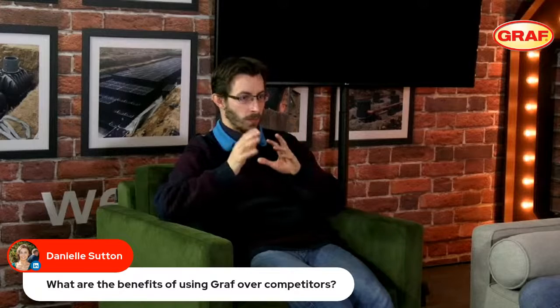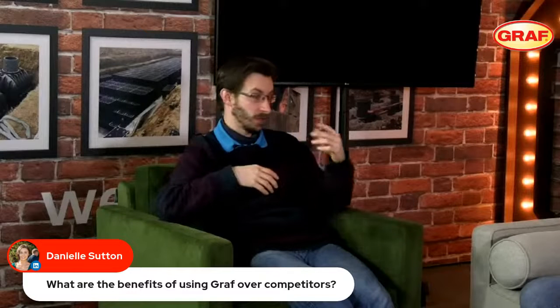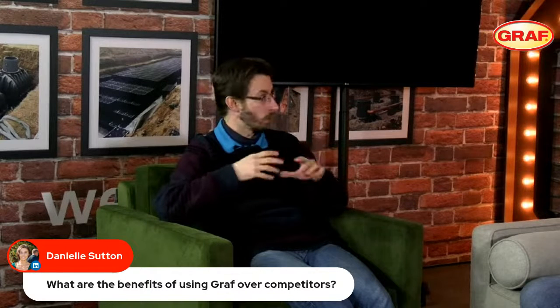This gives us a very good level of oxygen for breaking down organic material, certainly the carbons and stuff like that, but it doesn't really give us the ability to tackle the nitrogen compounds. So by being able to drop the oxygen level down, we can treat those nitrogen compounds a lot more effectively, and that gives us in the end a much better quality of discharge. So certainly in relation to reduction of total nitrogen, with being an SBR system, we have that control to do so.